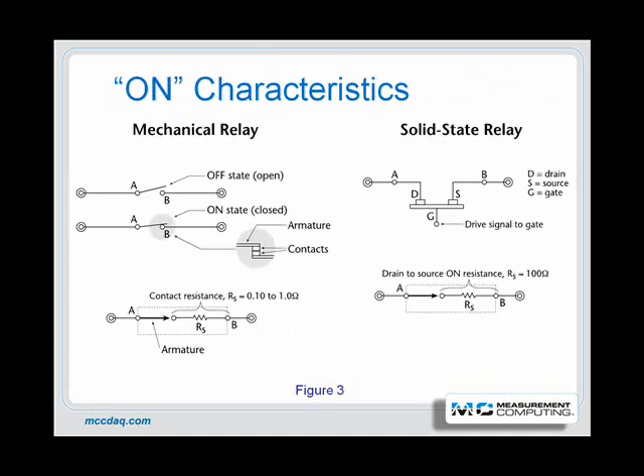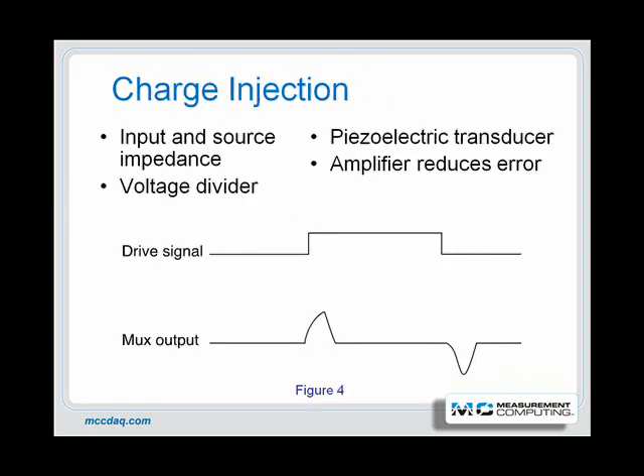Another characteristic that varies between mechanical relays and solid state switches is called on resistance. An ideal mechanical switch or relay contact pair has zero on resistance, but real devices such as common relay contacts are 10 milli-ohms or less. A quality analog switch can be 10 to 100 ohms, and an analog multiplexer can be 100 to 2,500 ohms per channel. The on resistance adds directly to the signal source impedance and can affect measurement accuracy if not compensated.